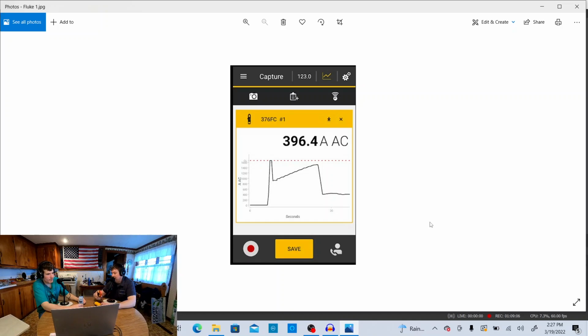So this is a 350 horse motor starting and running. The running current on that motor is 396 amps at 480 volts.